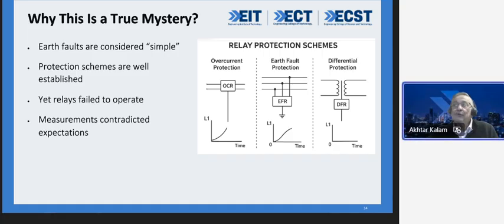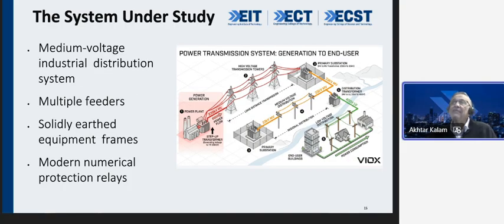So let us go back to my study that I have started and look at my system. I've got a simple system, my friend, a medium voltage industrial distribution system where there's a generation, there's a transmission line, there's a load, all that stuff. It has multiple feeders. The equipment frames are solidly earthed. The numerical protection relays are pretty modern. So I don't think there's anything exotic that I'm talking about. This is a standard industrial medium voltage system, and it has been designed to the best practice.